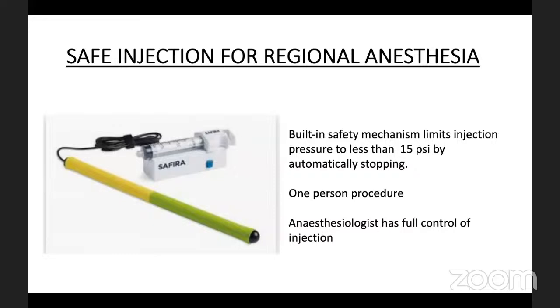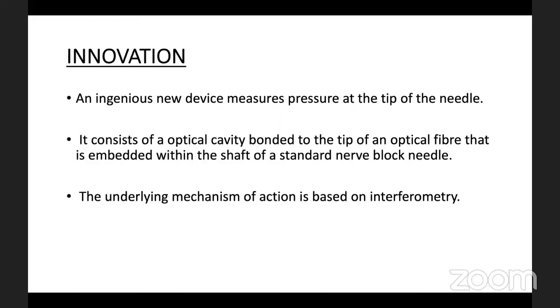The advantage here is that it has a built-in safety mechanism that limits injection pressure to less than 15 psig by automatically stopping. Also, I don't need an assistant. I would be giving the local anesthetic myself. I have full control of the injection. As for innovation in this field, there is a new device in which the pressure monitoring is at the tip of the needle itself. It consists of an optical fiber at the end, which has an optical cavity, and it measures the pressures.